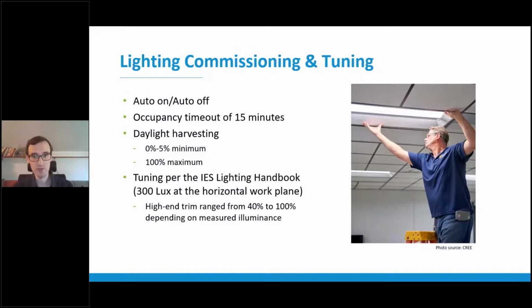So these are some of the primary variables that were standardized for the commissioning and tuning of each system, and these included auto-on, auto-off controls with occupancy timeouts of 15 minutes across the board. Daylight harvesting, the minimum ranged between 0 and 5% depending on system capability, while the maximum for all of them was 100%. Tuning was based on the IES lighting handbook recommendations for standard open office lighting level at the horizontal work plane, which was 300 lux. As a result, high-end trim ranged from 40% to 100% of the total output of each fixture.